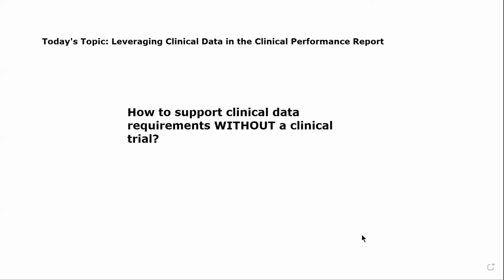But in some cases, because this is a brand new requirement for IVDR, it may eventually be necessary to start proactively collecting those clinical data sets by looking at hospital databases or registries or things like that.